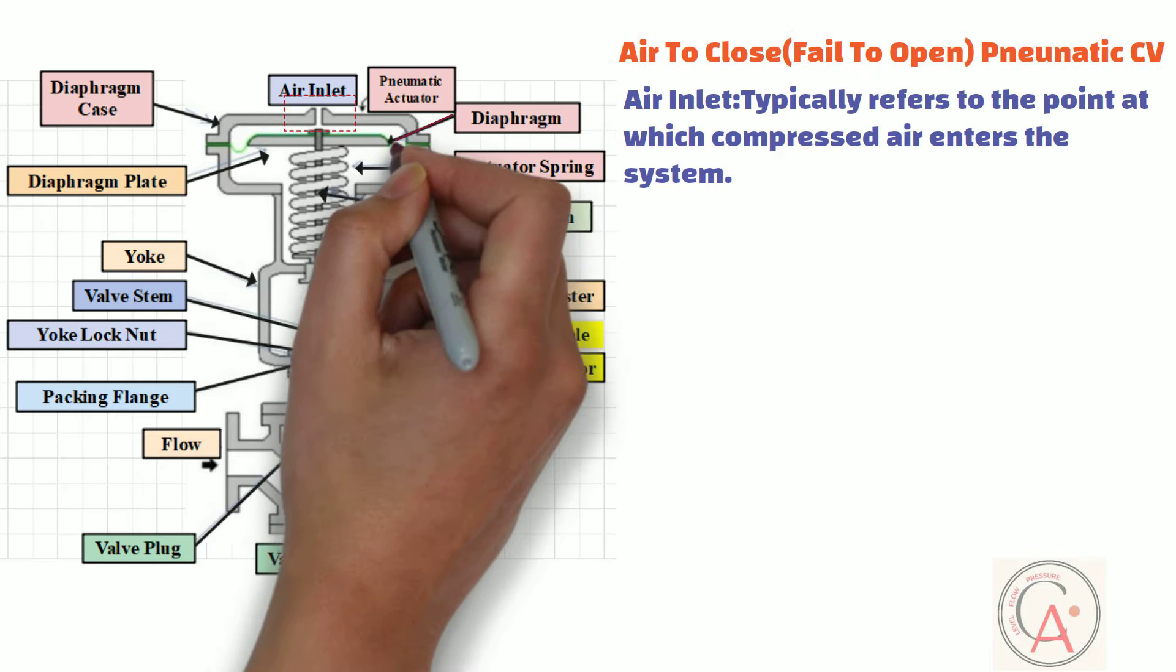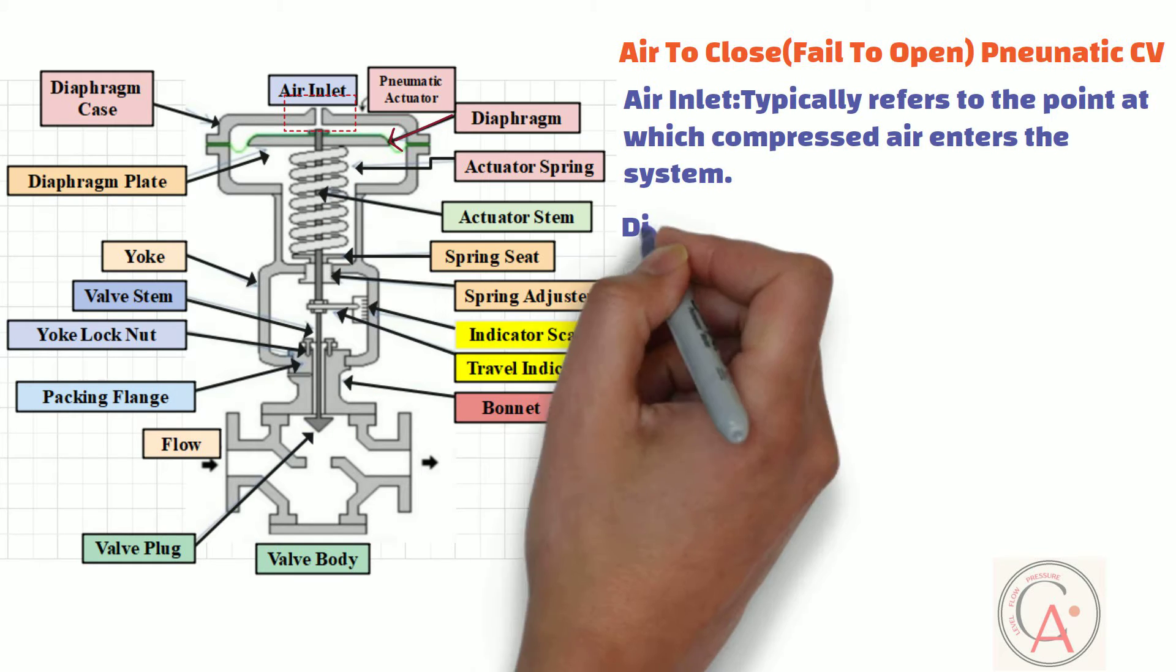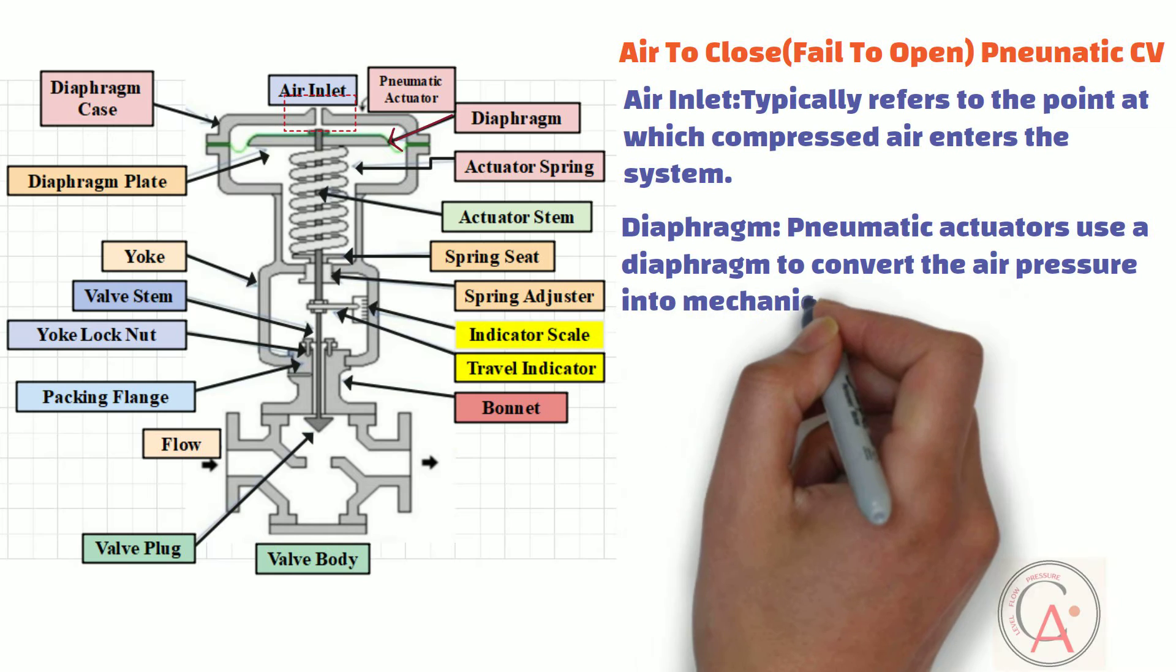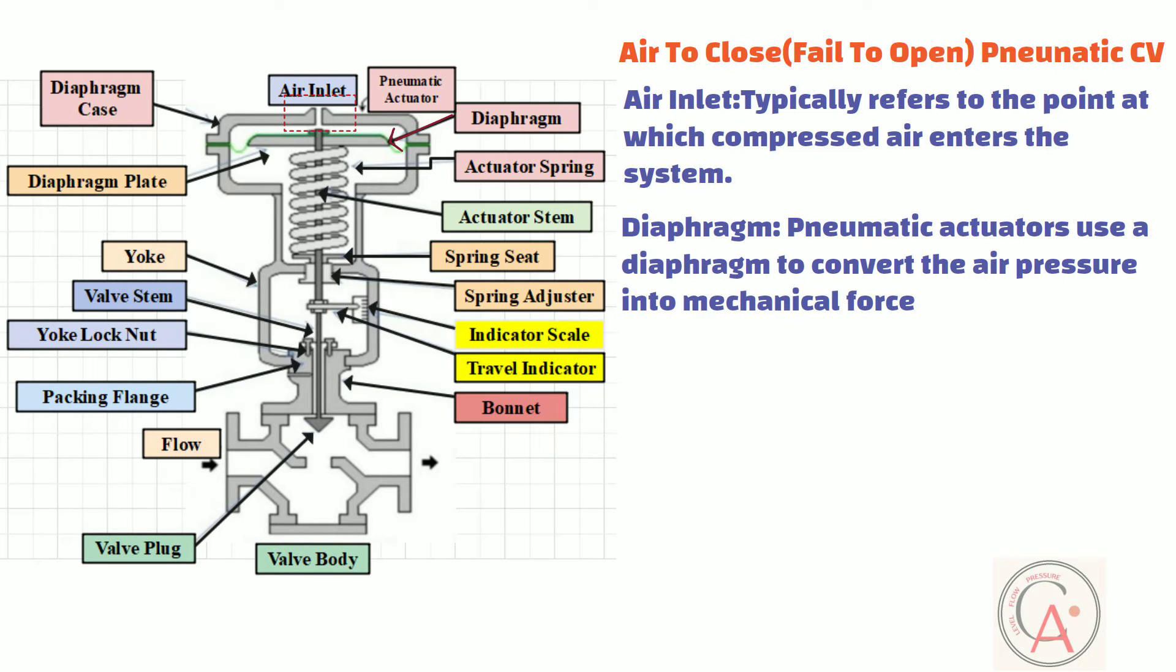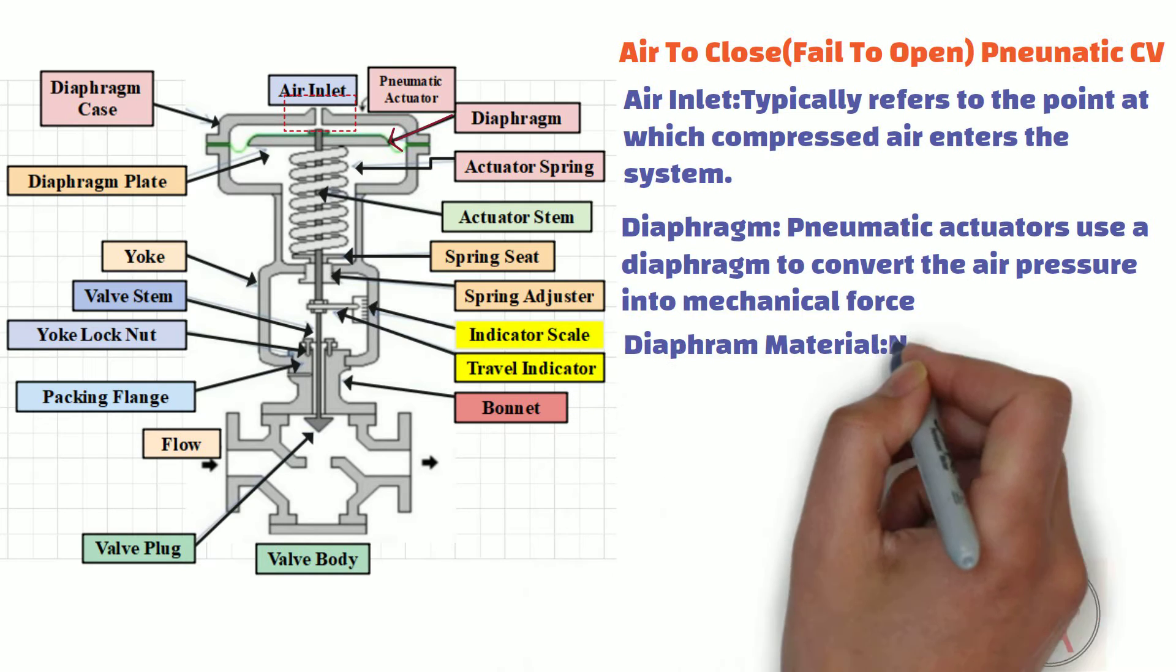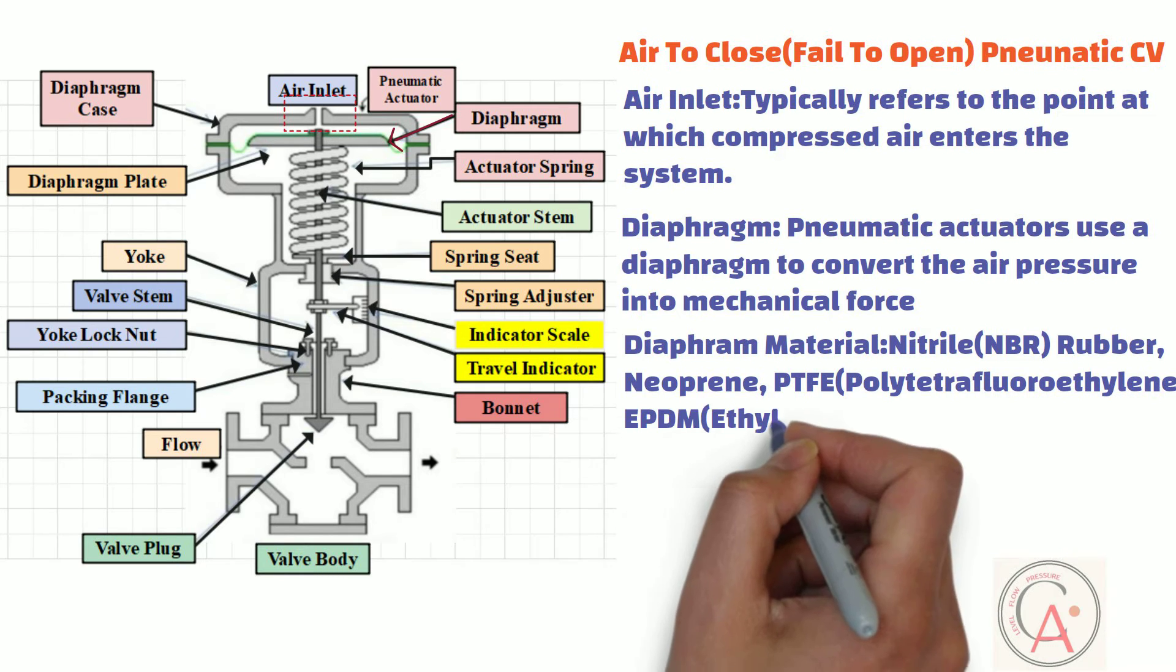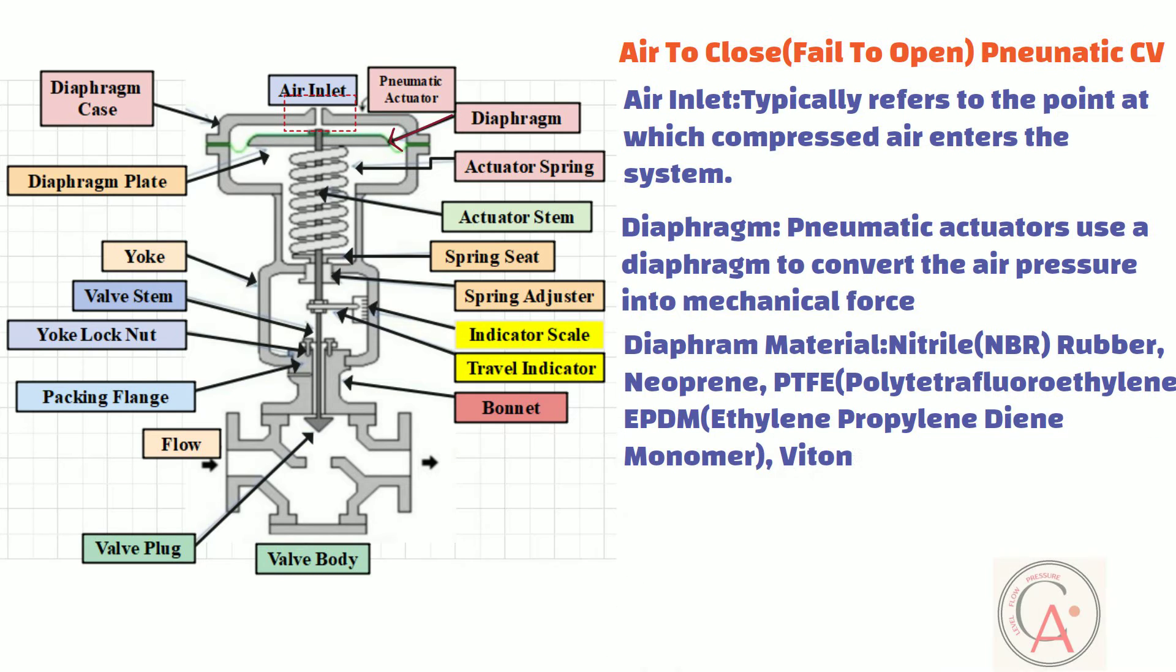The second most important part is the diaphragm. Pneumatic actuators often use a diaphragm to convert the air pressure into mechanical force. The diaphragm separates the actuator's air chamber from the valve body and moves in response to changes in air pressure, thereby positioning the valve plug. Nitrile rubber, neoprene, PTFE or polytetrafluoroethylene, EPDM or ethylene propylene diene monomer, and Viton are most commonly used as diaphragm material.